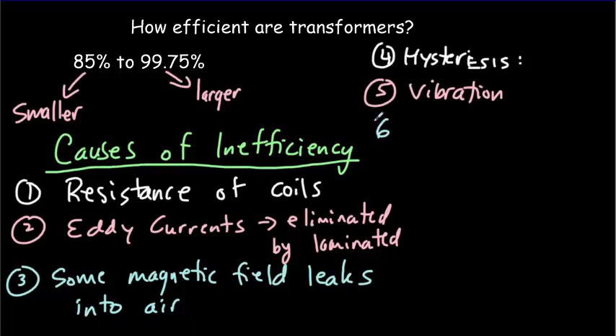And there's a sixth effect called magnetostriction. That has to do with the changing flux inside the magnetic core causing it to expand and contract very slightly, and that leads to losses as well. So in a good transformer, all six of these effects are reduced to an absolute minimum.